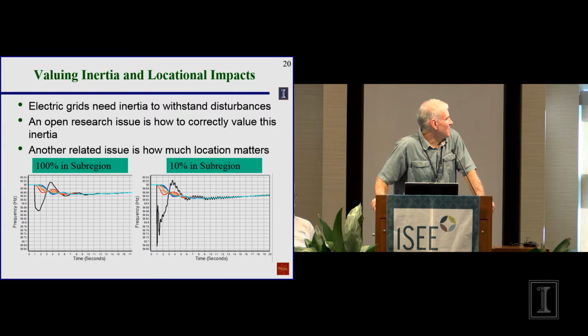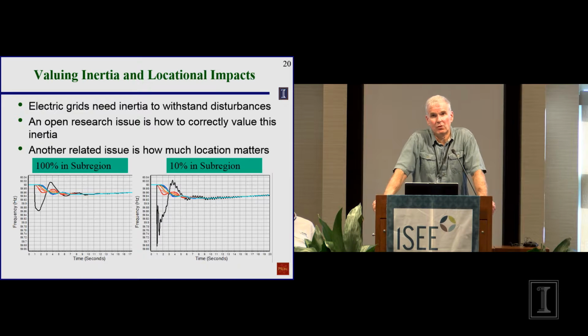Some of the research we're working on right now is trying to figure out how we value the inertia provided by devices like large nuclear power plants. If you take a plant and get rid of it, you've lost inertia on the grid - should that inertia be valued? Another thing we're looking at is whether the location of the inertia matters. What we're finding is that if you take out too much inertia in regions of the grid - say if Illinois totally got rid of its base load generation and went entirely wind and solar - it might have implications.